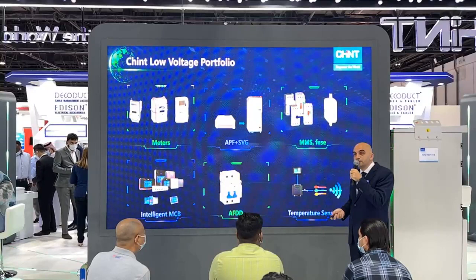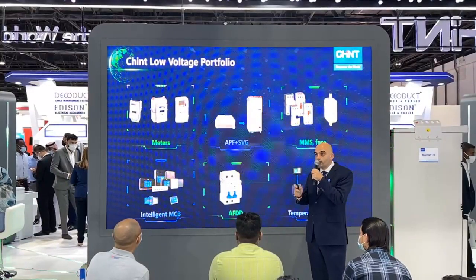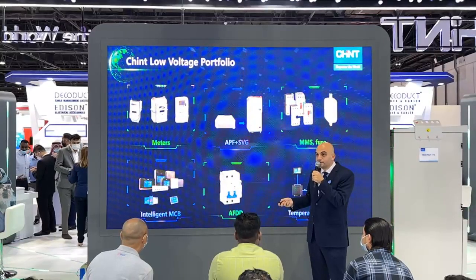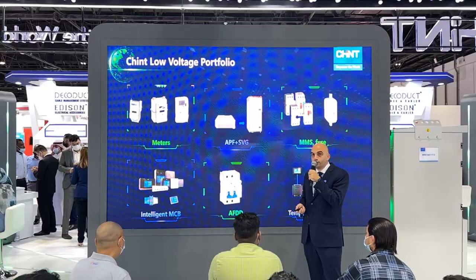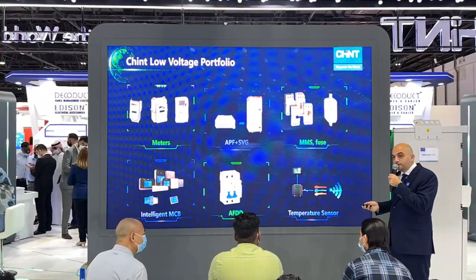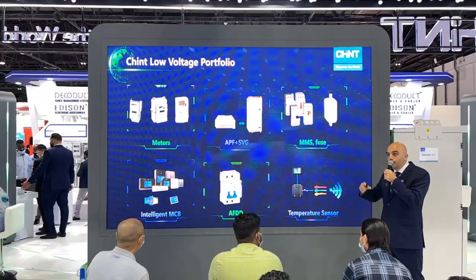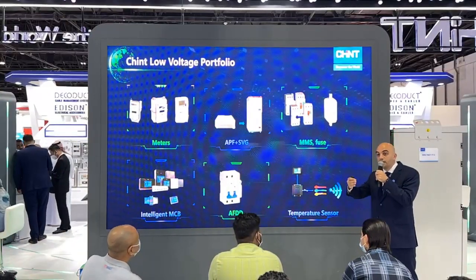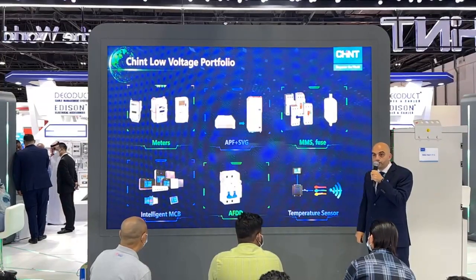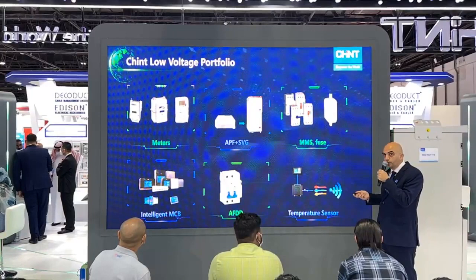We have intelligent MCBs connected through 3G, 4G, or Wi-Fi, visible at section 4. These are connected to software with live monitoring of the breaker's status. We also have AFDD — arc fault detection devices — and temperature sensors. These temperature sensors are placed on the bus bar and broadcast live temperature data through Wi-Fi to the low voltage switchgear monitor. There is a live demonstration available in section 1.